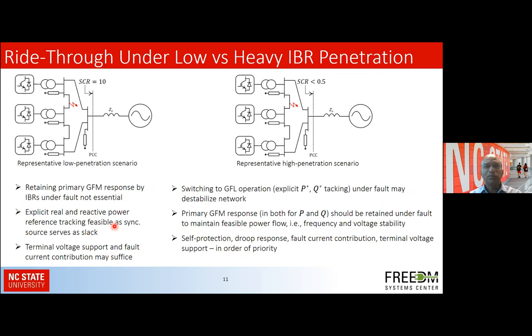So the ride-through, in terms of the high versus low penetration, just to explain it a little more here. Looking from the inverter side, the IBR resource side, if the short circuit ratio is large, it means it's a strong interconnection. If there is a fault anywhere here, the synchronous generation can supply the fault current through this strong interconnection. But when the short circuit ratio is low, it's a weak interconnection, and the grid impedance is high, then this unit should be designed so that it can support the load currents locally as well as the fault current.